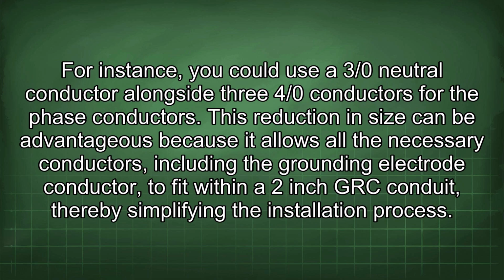For instance, you could use a 3/0 neutral conductor alongside 3 4/0 conductors for the phase conductors. This reduction in size can be advantageous because it allows all the necessary conductors, including the grounding electrode conductor, to fit within a 2-inch GRC conduit, thereby simplifying the installation process.